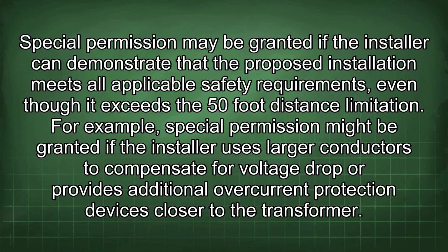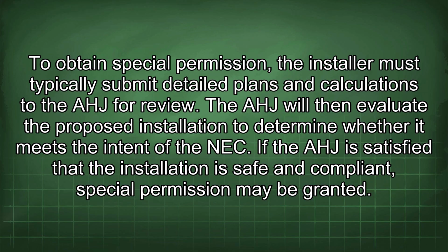For example, special permission might be granted if the installer uses larger conductors to compensate for voltage drop or provides additional overcurrent protection devices closer to the transformer. To obtain special permission, the installer must typically submit detailed plans and calculations to the AHJ for review. The AHJ will then evaluate the proposed installation to determine whether it meets the intent of the NEC. If the AHJ is satisfied that the installation is safe and compliant, special permission may be granted.